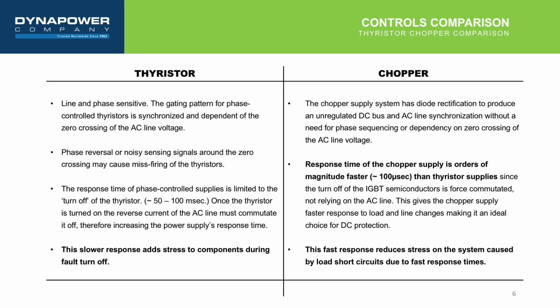On the other hand, IGBTs in the chopper topology are not phase dependent and do not require synchronization. Diode bridge on the front provides initial DC rectification without phase sensitivity. Transistor control is high-frequency PWM with fast response time, as the semiconductors do not need special turnoff. The response time is around 100 microseconds, 1,000 times faster than the Thyristors. The electronic boards used to control both topologies are developed, controlled, maintained and guaranteed by Dynapower. That gives us flexibility and confidence to supply and maintain our product and guarantee the life of spare parts for both chopper and high-power Thyristor rectifiers.